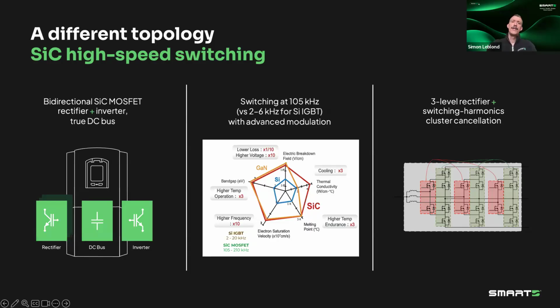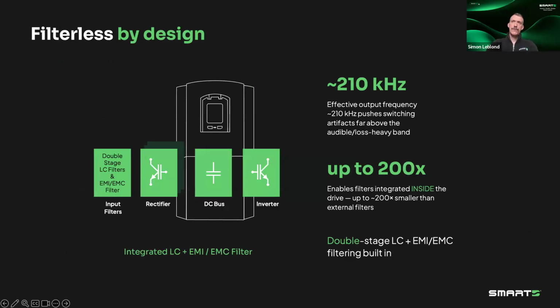And the reason why they've been adopted so massively by these industries is not only do they enable faster switching, but they also have higher power density and much lower losses. So when you take these specifications, you really get the potential for a whole new level of performance. And we've taken that and combined it with a multi-level architecture and, from an algorithmic perspective, with harmonic cluster cancellation. So you put all of these together, silicon carbide high switching frequency, the multi-level architecture, and the harmonic cluster cancellation, and you get a solution that has 200 times smaller filters directly built into the drive.